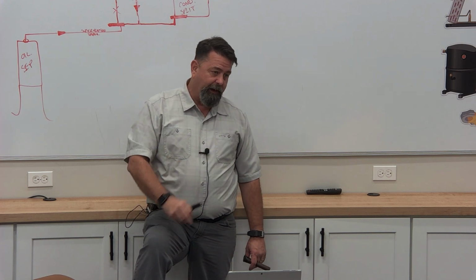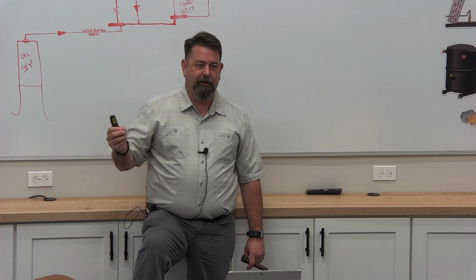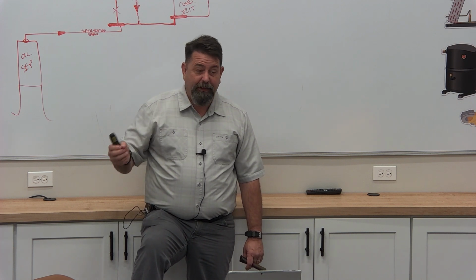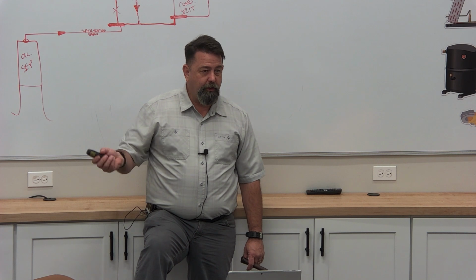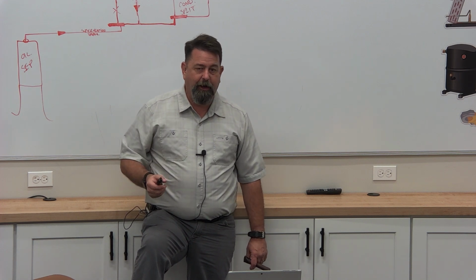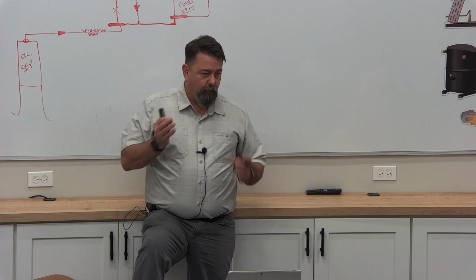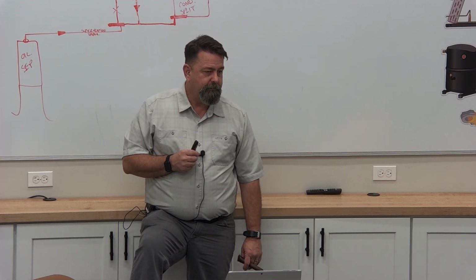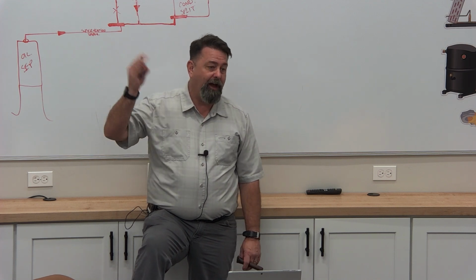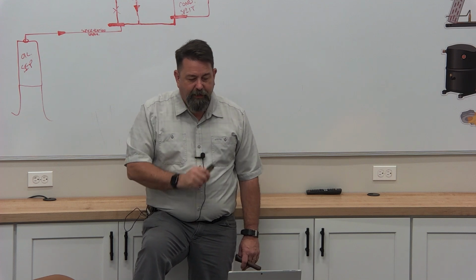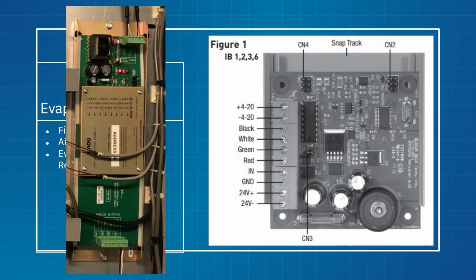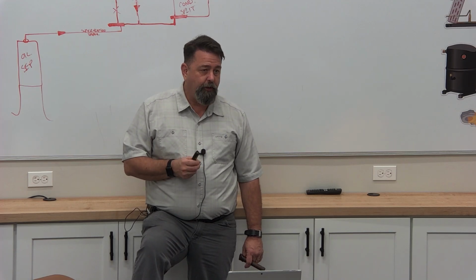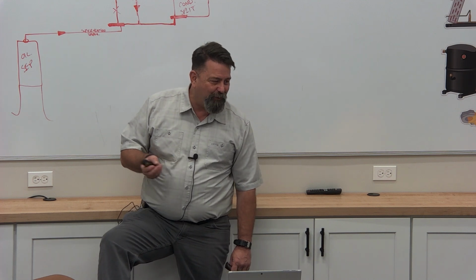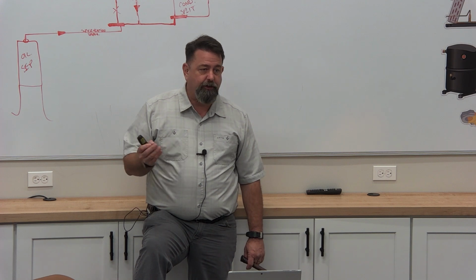So we can use this analog output module to also control pulse width modulation. Oh man, I'm talking back to like week 2. But that means digital compressor. I can load and unload a Copeland digital compressor with an analog output module, because I can tell it 30%, and it will say 30% of 20 seconds, turn on. I can do that. I can dim my lights 70% with this. In this case, all I'm doing is sending a 0 to 10 volt signal, and it's direct. So 0% is 0 volts, 10% is 1 volt, 100% is 10 volts. So add a 0 to your voltage and that's your percentage.